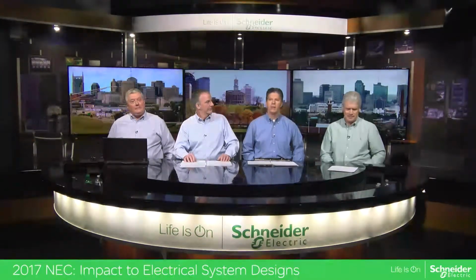And 230.95 is where we've had our traditional ground fault protection of equipment requirements. You know, the requirement that you install ground fault protection of equipment to protect the equipment, it reduces the equipment damage for the most common fault within the power system, which is a ground fault. So that is done when the equipment is installed on site. So what's changed here in the 2017 is the test method.